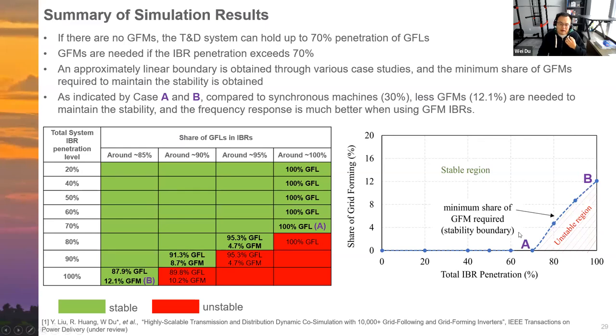There are 2 points I'd like to highlight. For case A, if we only have grid following inverters, when the grid following inverter penetration goes up to about 70% and the rest are synchronous machines, this is a stability boundary point. That means the 30% synchronous machines can hold the rest of the 70% grid following inverters. But at point B, for this 100% IBR system, we only need 12% of grid forming inverters to hold the rest of the 88% of grid following inverters. So for grid forming inverters, you need fewer of them in the system compared to synchronous machines to maintain the frequency stability.